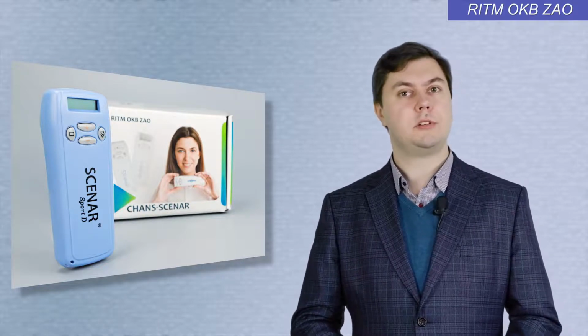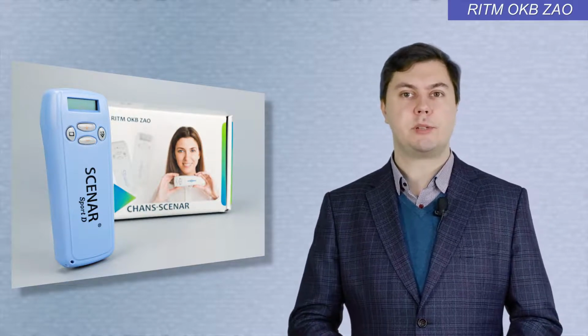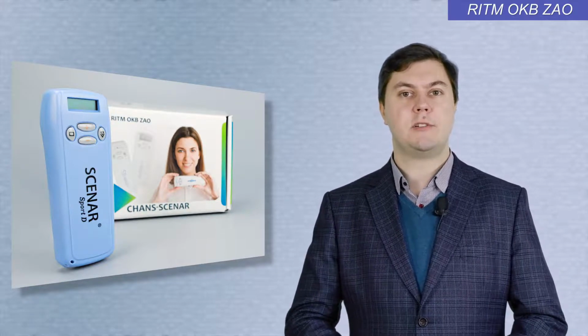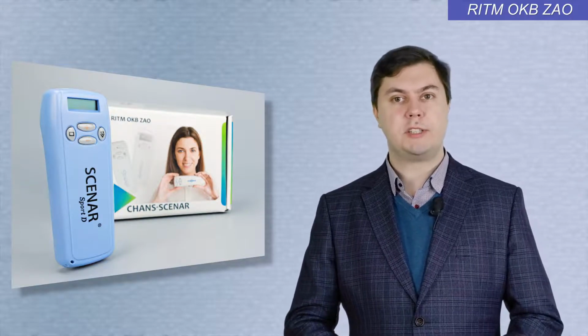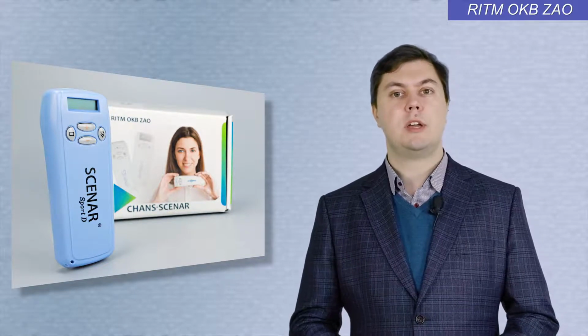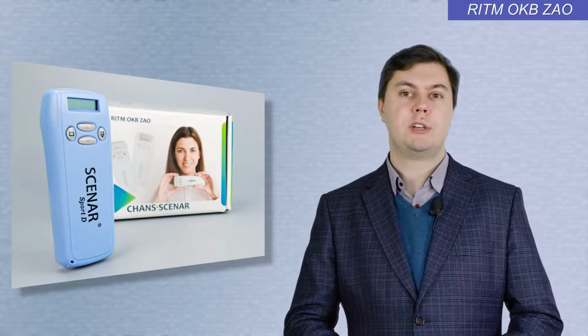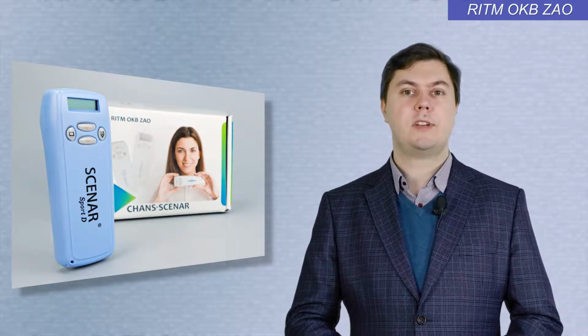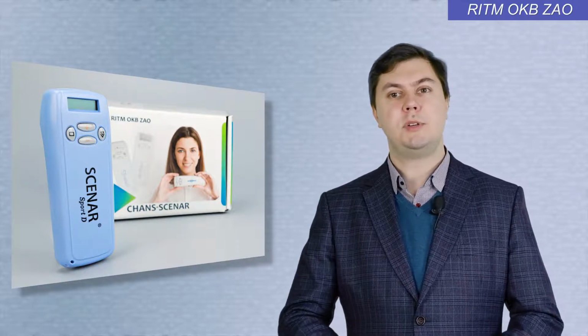Preset 2, or P2, or systemic. This preset is intended for systemic treatment. It is aimed at the interaction with the nervous system and has the effect of general regulation. When you are in the default state, before you activate this preset, you need to set the comfortable level of energy. In this mode, first phase is the high-frequency treatment, second phase is the mid-frequency treatment, and the third phase is the low-frequency treatment.